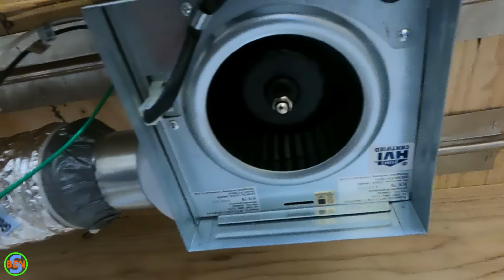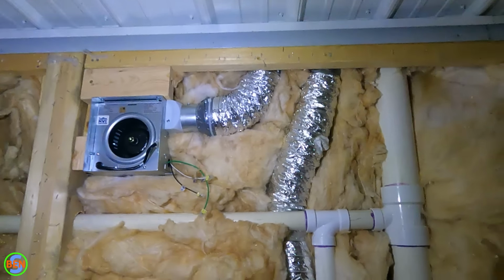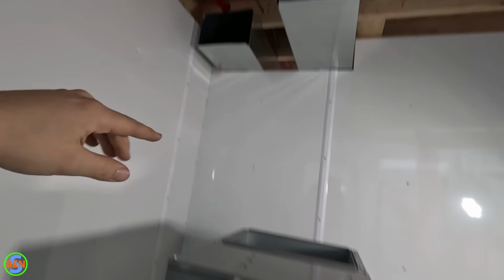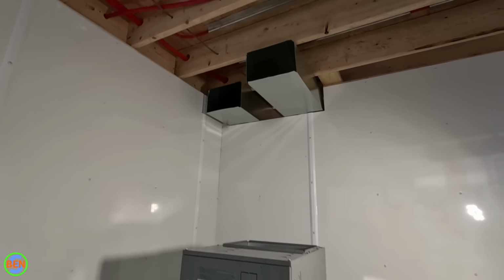Extra air coming into that room is going to be vented out through either the bathroom fan or just out through gaps and cracks in the structure itself, which is not really an issue, and it keeps the bathroom much fresher, and then you're not pulling that return air back into the rest of your building from the bathroom, which is where you don't want to be pulling air from.